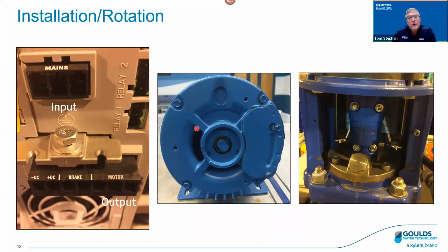Okay, so let's talk a little bit more about rotation in terms of our installation process. So here's a drive. We can see the input is titled mains. The output is titled motor. And here is where we would change the rotation if we have a drive. So we're going to go to the output of the drive, reverse any two of the three leads. And that is going to change the rotation. So that's how to change the rotation.